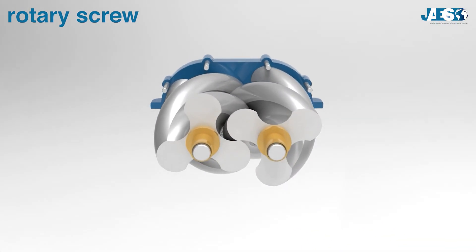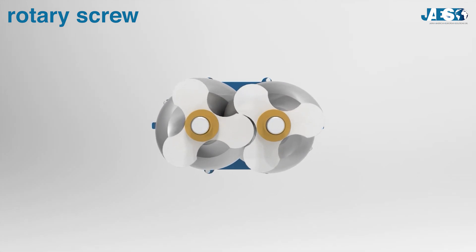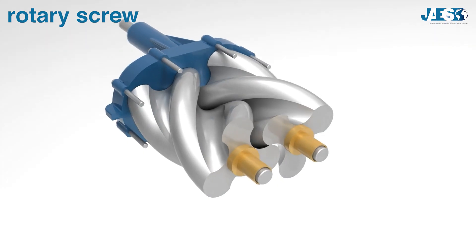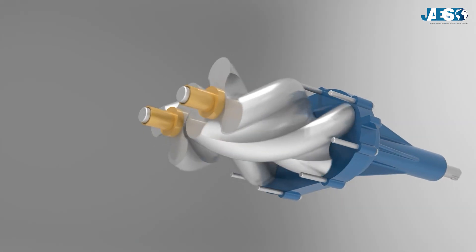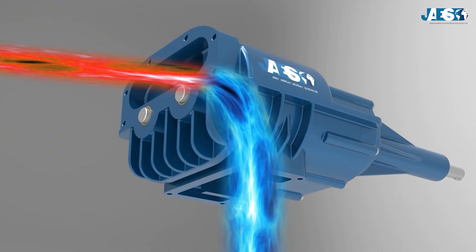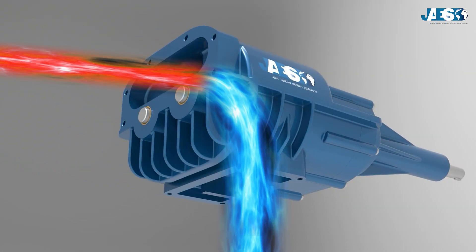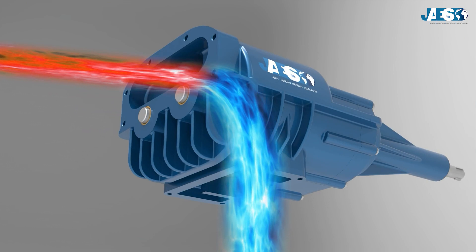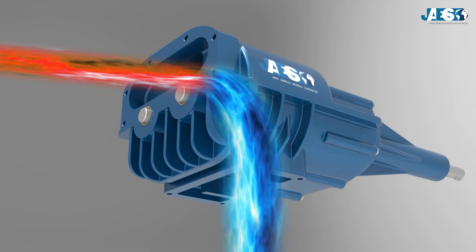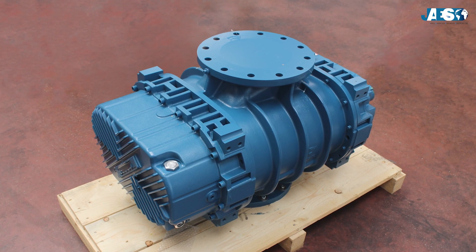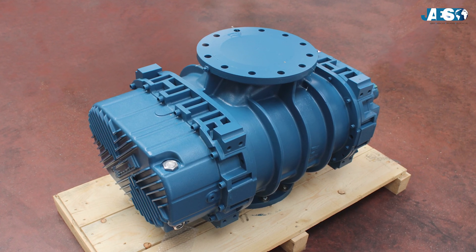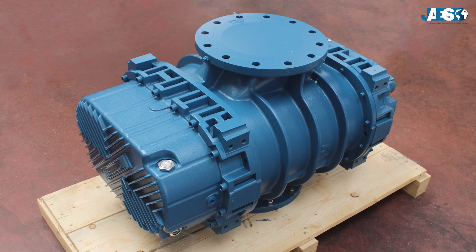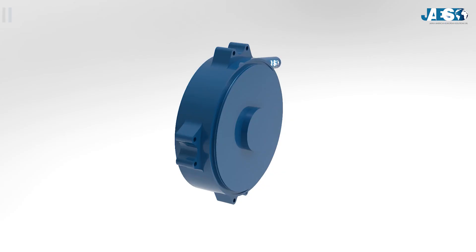Similarly, in the rotary screw compressor two reverse-pitch screws are connected to each other so as to develop through the core of the compressor a cavity progressively moving from the intake to the exhaust area, decreasing the volume and thus compressing the gas. Having little stress, this mechanical variety is suitable for continuous use and has good performance.